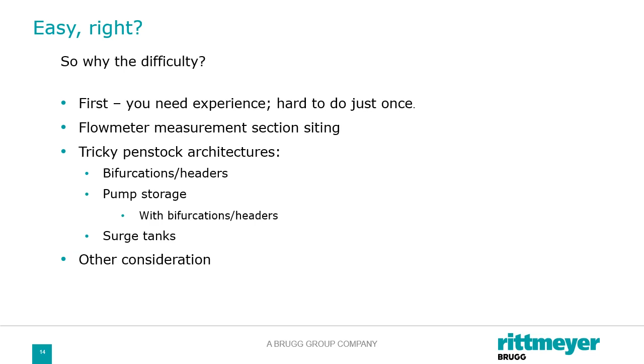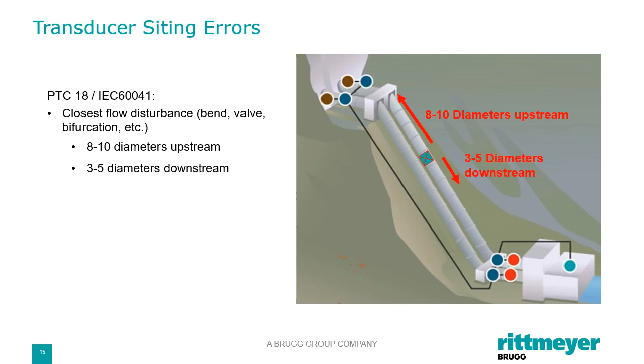So taking them one by one, the transducer siting, again, matters here. Per the standards, you need a straight section of pipe to install the transducers, to put that measurement section in. You typically want 8 to 10 diameters of straight pipe upstream and 3 to 5 down. So if we look at a real world example of this, we might want to put the flow meters in these sections because this is a generate only penstock structure. And so this is a nice straight section, and down here is another nice straight section. So those would be good from a flow meter only consideration.